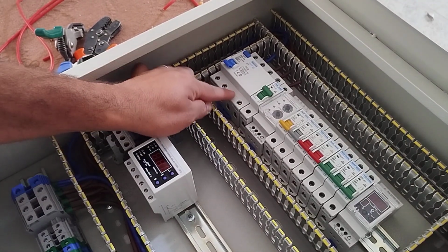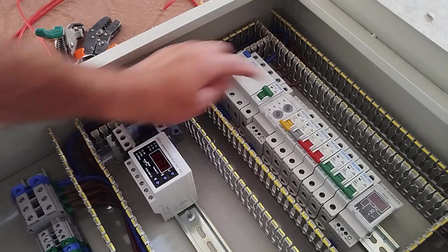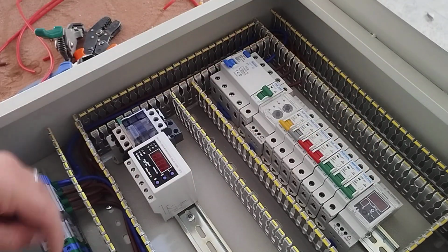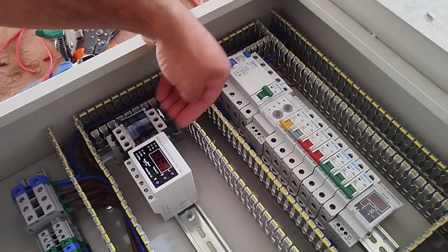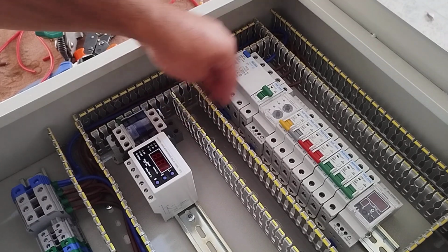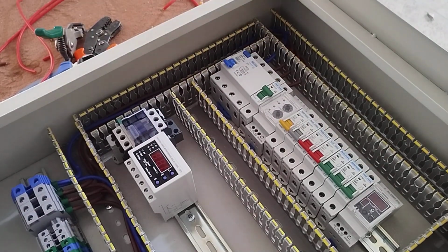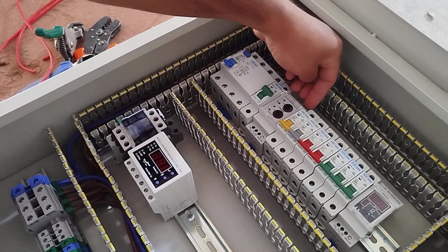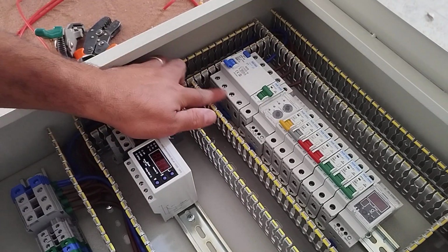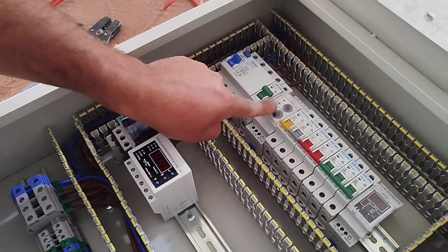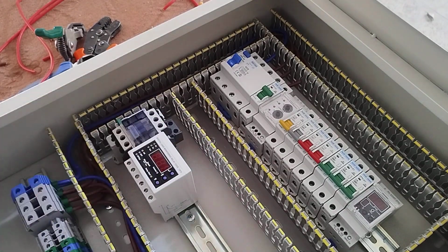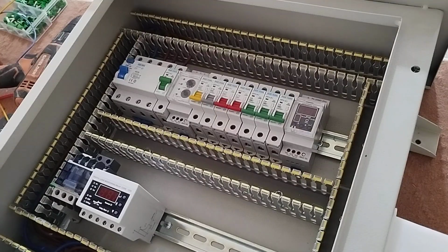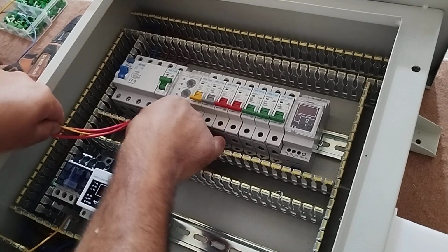In this step, we connect three phases from the output of the RCCB switch to the input of the single-phase miniature switch. Also, we connect three phases from the output of the RCCB switch to the input of the contactor. Also, we connect three phases and neutral wire from the output of the RCCB switch to the input of the three-phase monitoring relay. This is for the first phase.